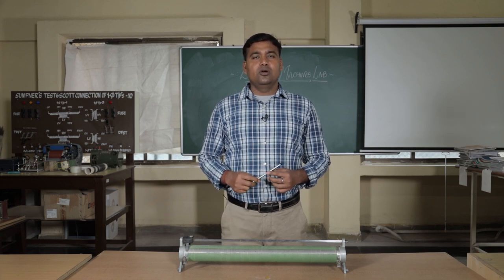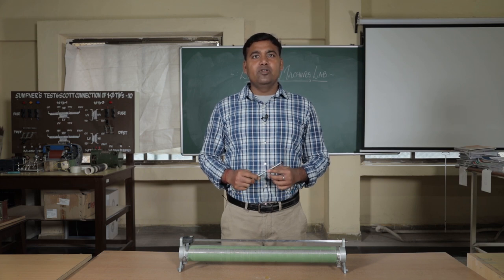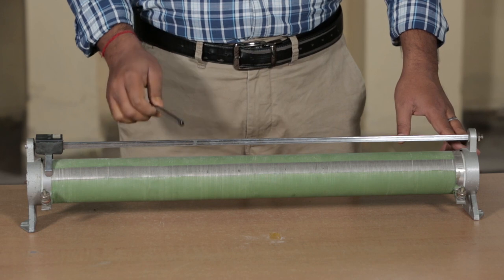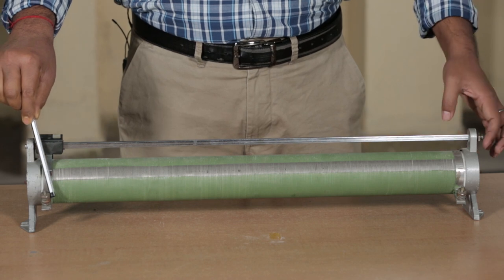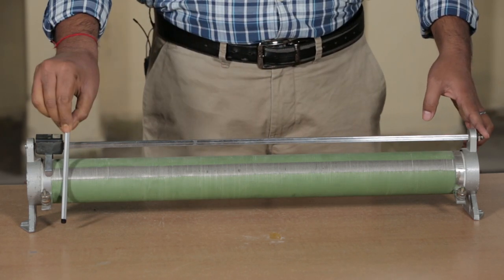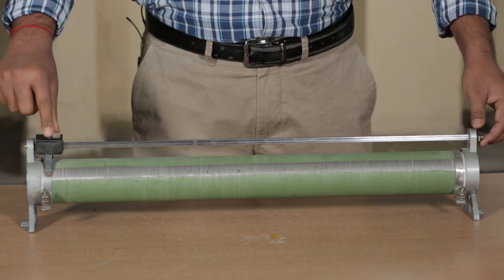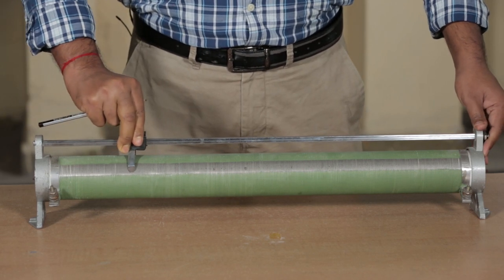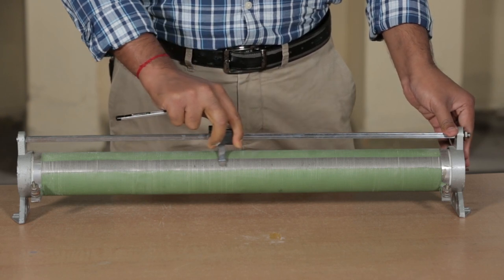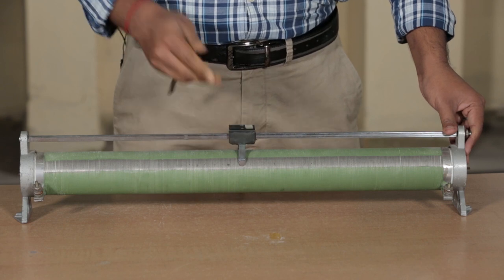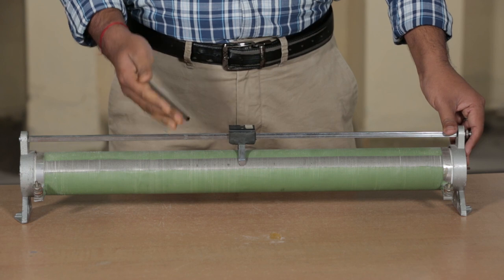This is a rheostat. Generally, in a shunt motor, we have to control the speed using the armature control method. To vary the armature resistance, we use a rheostat. A rheostat is a variable resistance which has two points — one is a fixed point and another is a variable point. Any of the points can be used as a fixed point and the other as a variable point. By varying the slider, we can vary the resistance. When we want to cut off the resistance, we move towards the fixed side; when we want to add resistance, we move towards the other side. This can be used to vary the resistance and vary the current.